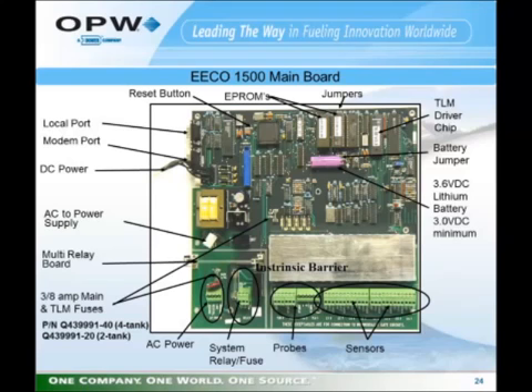And above that, we see the 2 external 9-pin ports that are standard on the board, one standard local, one standard external modem. In the upper right corner, you'll see some integrated circuit chips that are labeled. Those are the EEPROMs, the memory chip, the TLM driver chip, a PAL chip, and then you'll also see the battery, a 3.6 volt lithium battery for memory retention. That battery is good down to a level of 3.0 volts DC minimum.